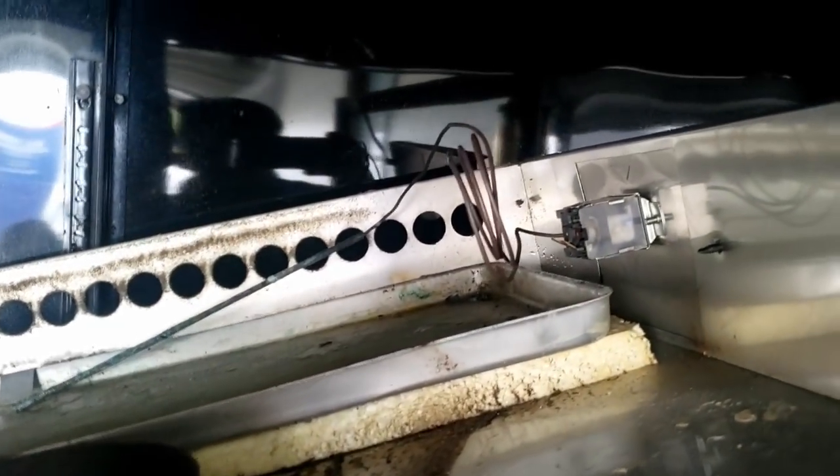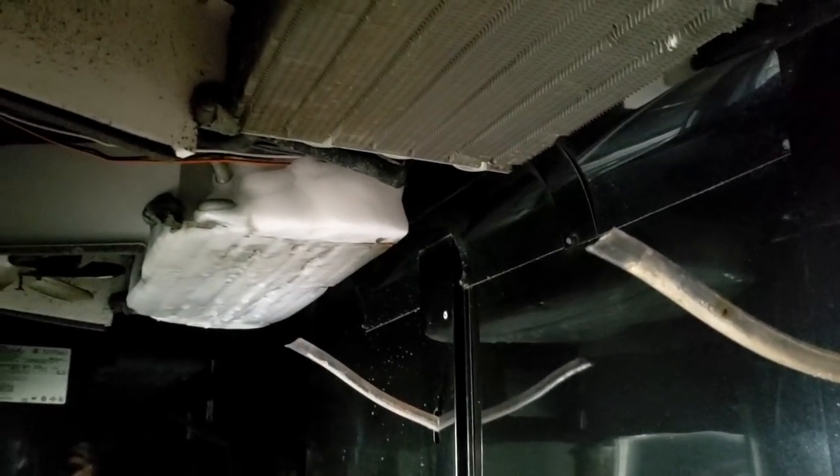Got one little bracket here in the middle to get out. One of the first things I noticed is the evaporator over there is frozen — that could just be low on charge. It had enough to freeze that one but this one didn't have enough, or it was good enough.